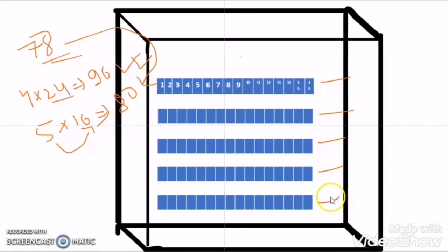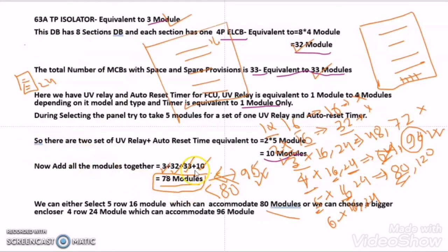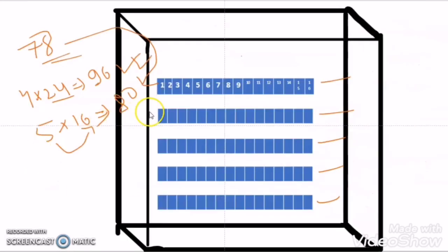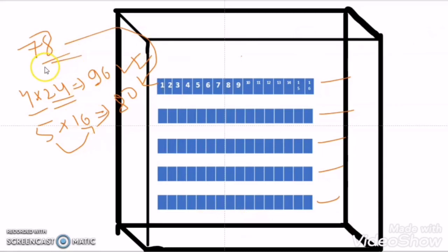I have selected a 5-row 16 module DB enclosure to accommodate my requirement of 78 modules. If there is a provision for future expansion, then you may choose the 4-row 24 module DB enclosure to accommodate 78 modules with more headroom.